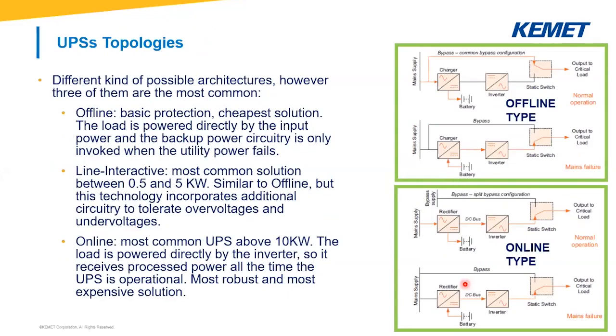There are hundreds of different architectures on the market. However, we can say that three of them are the most common. The first one is the offline topology. It gives basic protections and is the cheapest solution. The load is powered by the input power and the backup power circuitry is solely invoked when utility power fails. As you can see in the scheme on the right, during normal operation the switch is up, meaning power comes from the mains. The UPS is not invoked at all — it's just attached to mains to recharge the battery. If there is a failure in mains, the switch goes down and power comes from the inverter and the battery.